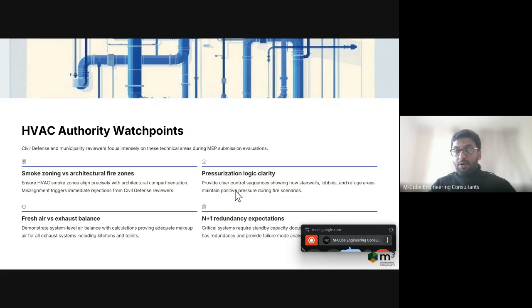Generally, they check your design on the schematic diagram for whether you have a relief valve for the staircase, in case the pressure becomes too much, and whether you're maintaining the 50 pascal pressure difference with the relief valve. So the authority is looking specifically for this point on your riser diagrams.